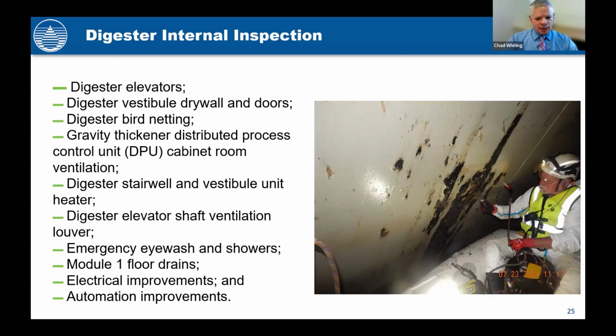Annually, we take them apart to change the ends on the heat exchangers, and anytime we do any work on that heat exchanger that's attached to the primary loop, it's like a fire drill to get it back online if it happens in the wintertime, because we don't want to lose the temperature in the digester. So we want to eliminate that urgency and have redundancy there to be able to do that project a little more controlled.